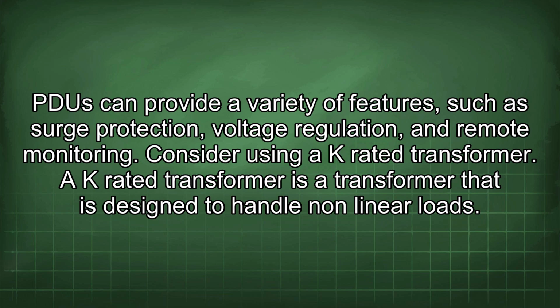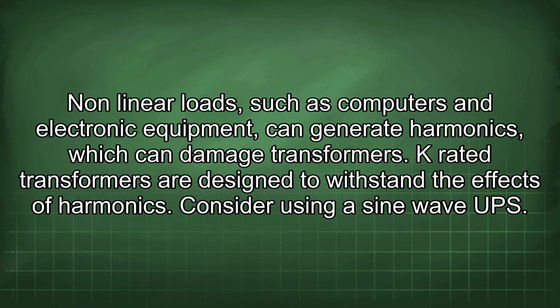Consider using a K-rated transformer. A K-rated transformer is a transformer that is designed to handle nonlinear loads. Nonlinear loads, such as computers and electronic equipment, can generate harmonics, which can damage transformers. K-rated transformers are designed to withstand the effects of harmonics.